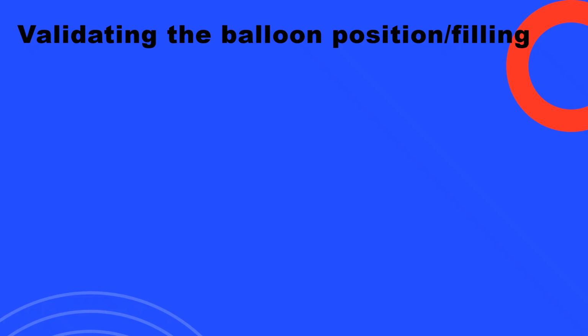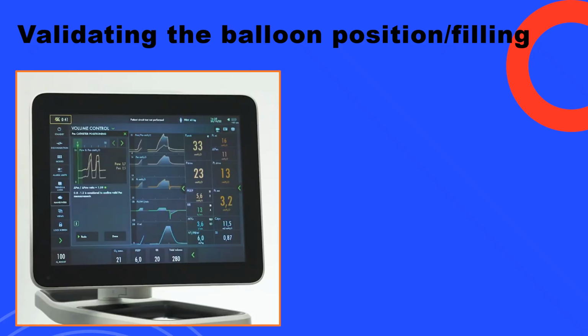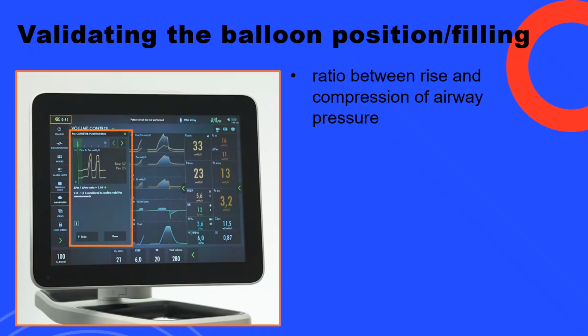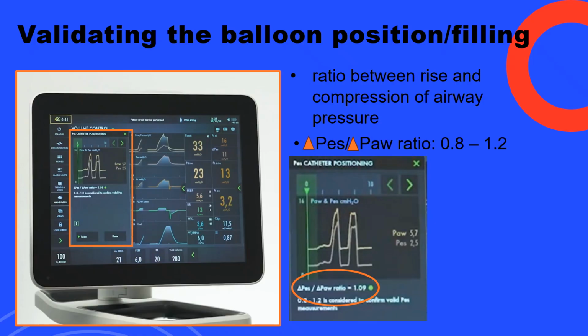After the maneuver has been performed, the Servo-U will calculate the ratio between the rise and compression of airway pressure. This reflects the difference or the ratio between the changes in esophageal pressure and airway pressure. The pressure ratio should be between 0.8 to 1.2. And for this maneuver, a calculated ratio is 1.09, which is acceptable. And this validates the correct position and filling of the esophageal balloon catheter. This is important in calculating the transpulmonary measurement, since Servo-U automatically calculates it.